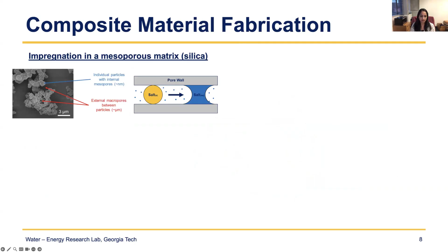And the silica has pores that are very small, so nanometer-size pores or mesopores. If you put salt into mesopores, if the salt forms a solution, it cannot leak out of the pores because of capillary attraction that keeps it within the pores. And so the salt remains within the mesopores of the silica. And then between the silica particles, we have larger macropores where water vapor can transport in and out. So essentially, we nano-confine the salts in a mesoporous matrix and allow the water vapor to transport. So this gives you a very stable composite that you can cycle hundreds of times.